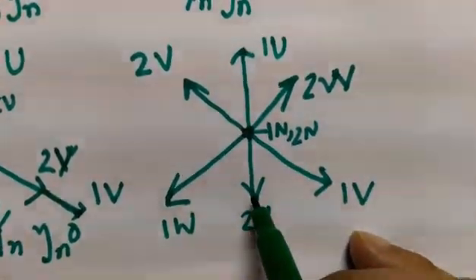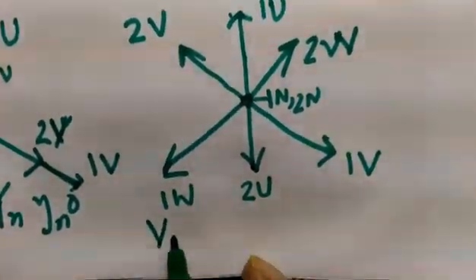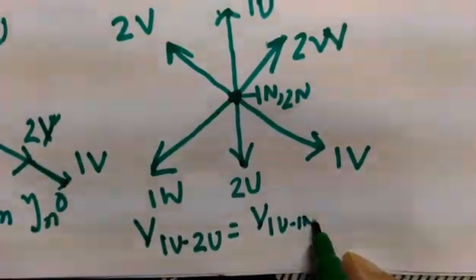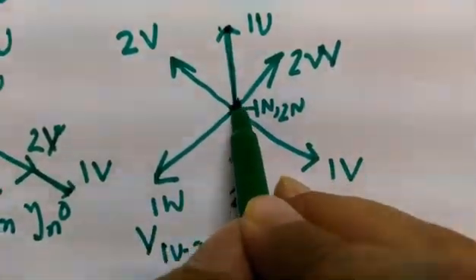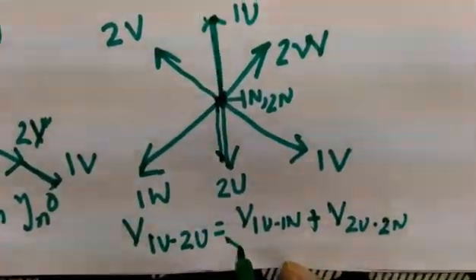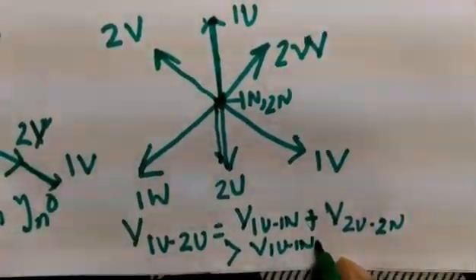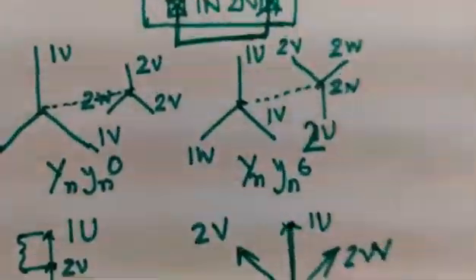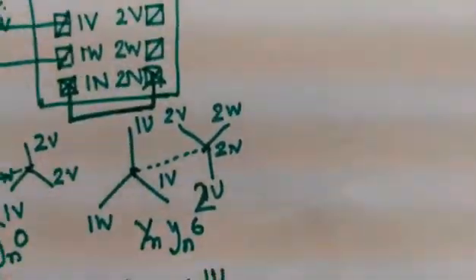So if the potential difference between 1U–2U, 1V–2V, and 1W–2W is less than the high voltage winding's phase voltage, then the vector group is YnYn0. For YnYn6, V(1U–2U) equals V(1U–1N) plus V(2U–2N), which is greater than V(1U–1N). So if the voltmeter gives a voltage rating higher than the phase voltage, the vector group is star-star 6; if lower, it is star-star 0.